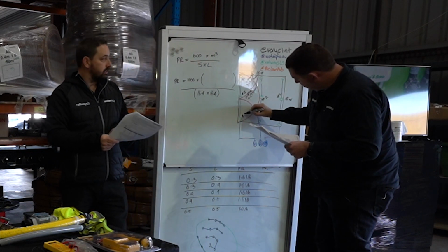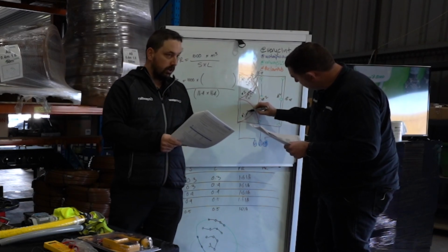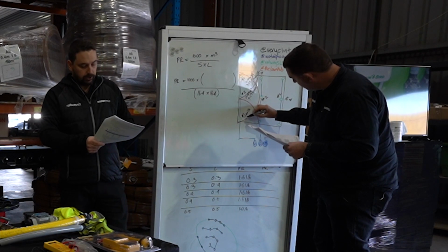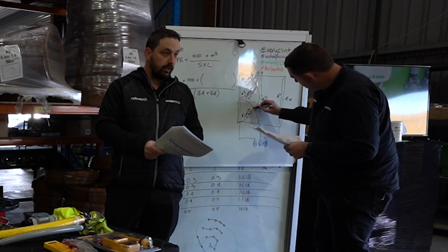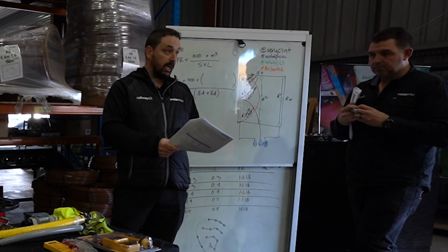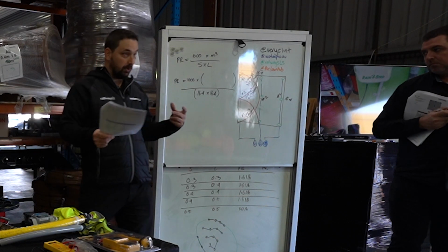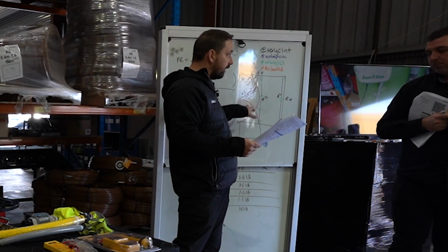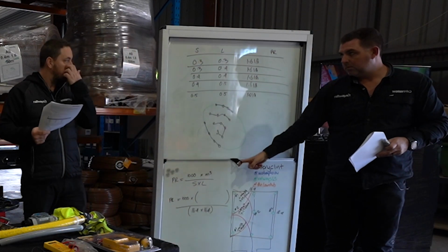Now, one thing to consider here, and this is more from a design standpoint, but what you do notice is we've compromised the distance we've been able to achieve. Originally we had 8.2 metres, and now we're seeing 6.4 metres with that smaller sprinkler. So this isn't actually going to throw as far either, but we try and get it as best as we can.